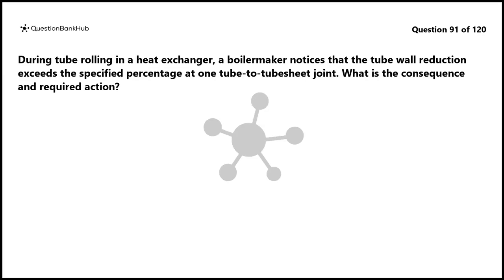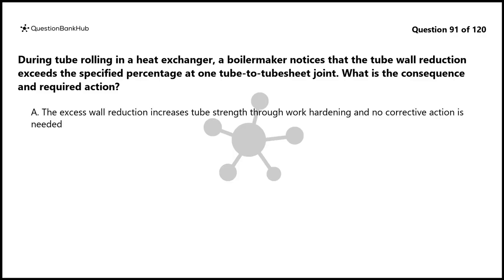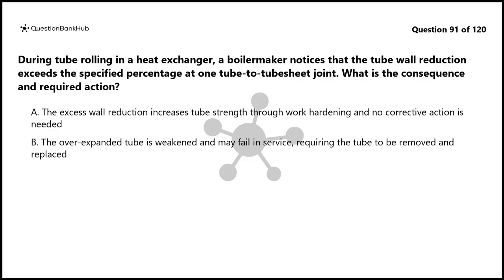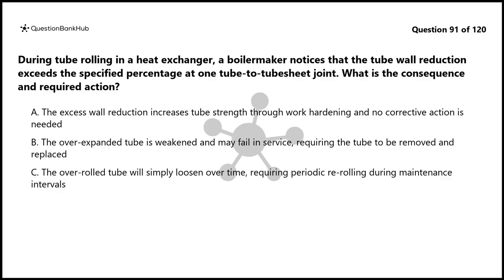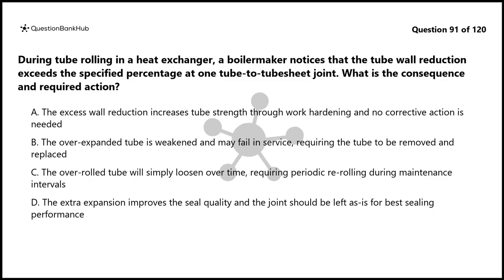Question 91. During tube rolling in a heat exchanger, a Boilermaker notices that the tube wall reduction exceeds the specified percentage at one tube-to-tube sheet joint. What is the consequence and required action? A. The excess wall reduction increases tube strength through work hardening and no corrective action is needed. B. The overexpanded tube is weakened and may fail in service, requiring the tube to be removed and replaced. C. The overrolled tube will simply loosen over time, requiring periodic re-rolling during maintenance intervals. D. The extra expansion improves the seal quality and the joint should be left as is for best sealing performance.